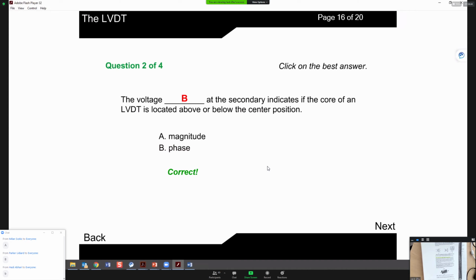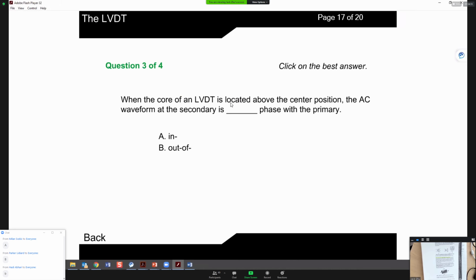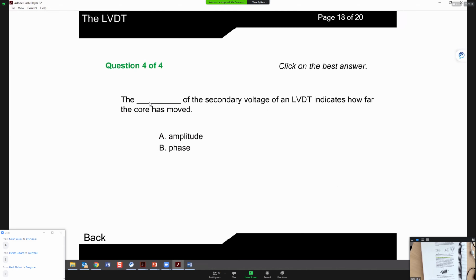Like we showed you, if on top, it's in phase with the primary side. If at the bottom, it's 180 degrees out of phase with the primary side. When the core of the LVDT is located above the center position, the AC waveform at the secondary, as we already talked about, is in phase with the primary. And what's going to tell you how far the core moved? That's the voltage value that's going to tell you how far the core moved, right? The phase just tells you if it's above the center or below the center.